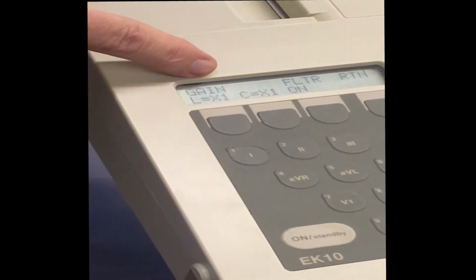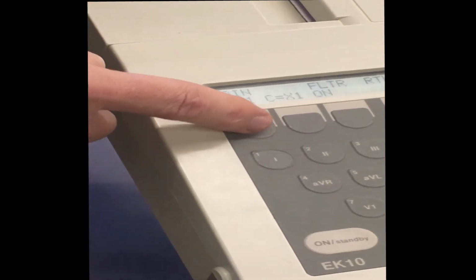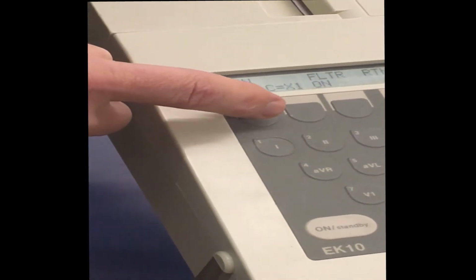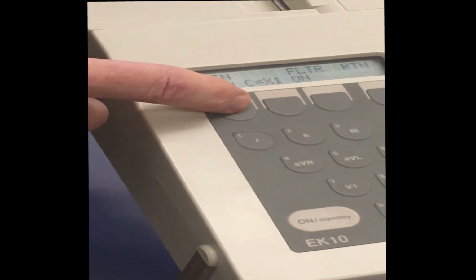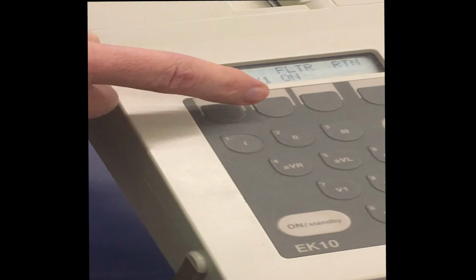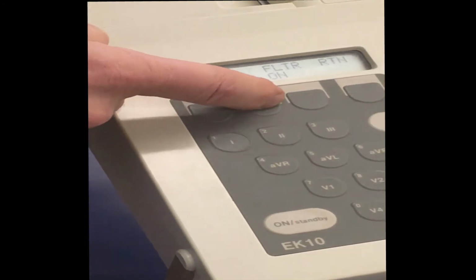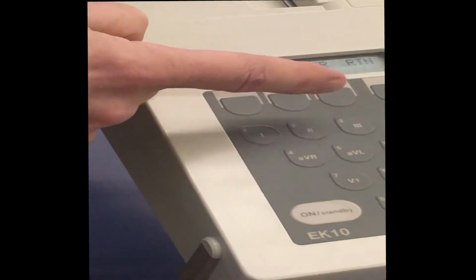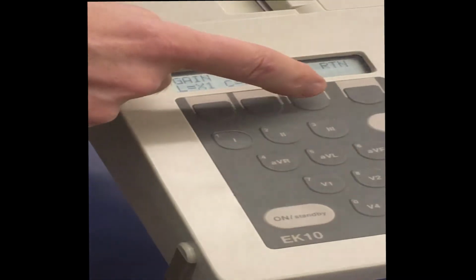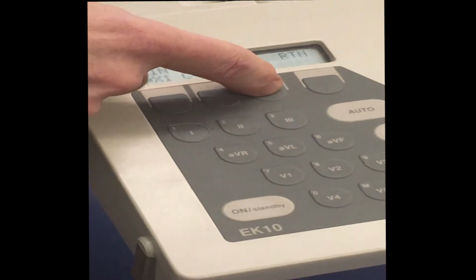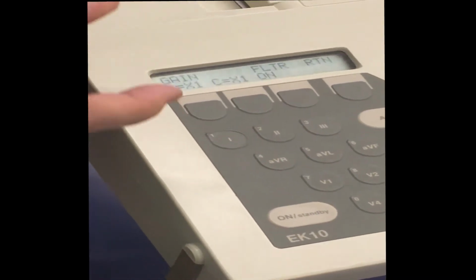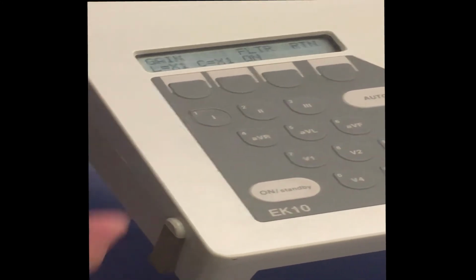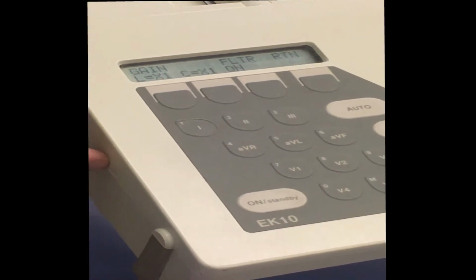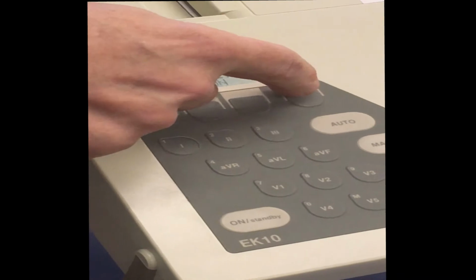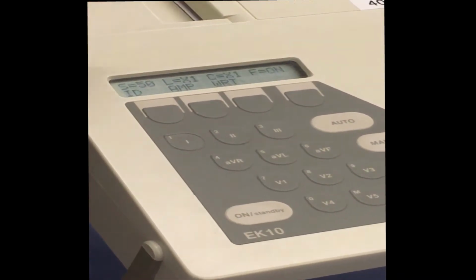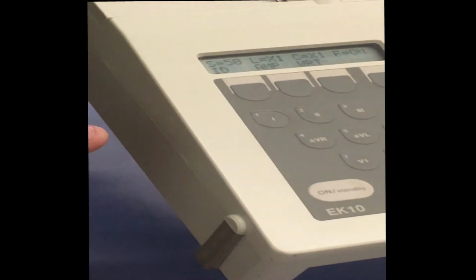If I want to change the limb gain, I push the button under the limb, and that allows me to change it to 2, change it to half, or change it to 1. I could do the same thing for the chest gain. I could half it or have it be 1. Or the filter, I can turn the filter on or turn the filter off. You always want the filter on unless you are doing the technical problem where I'm asking you to turn the filter off. And then when you set everything, you just hit return. So now you know that all your settings are correct.